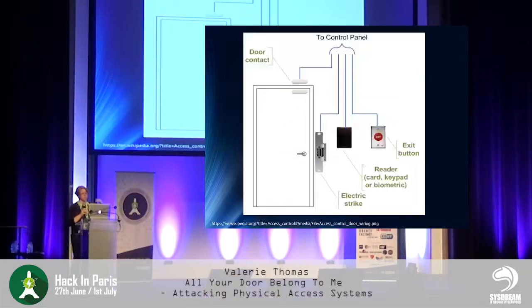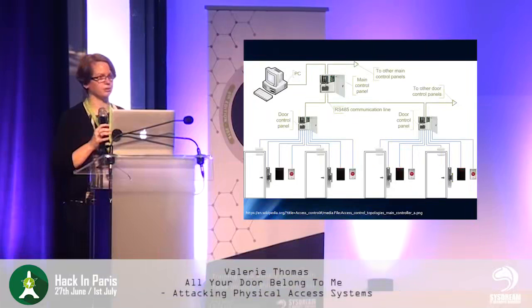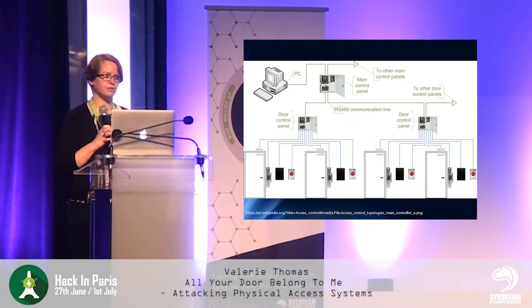The controllers have to be scaled because they can't hold very many inputs. So if we look at it from just a single perspective, it looks very basic. But once you start getting into multiple floors and multiple levels of the building, and you bring in things like elevators, it's a lot of inputs, and the controllers are pretty limited, even with buying the expansion pack. So you probably have at least 10 to 15 controllers in a 5 to 8 story building. It's definitely not just one device that's sitting in the closet somewhere. We have 15 devices that are in closets and under desks and in all random areas of the building.